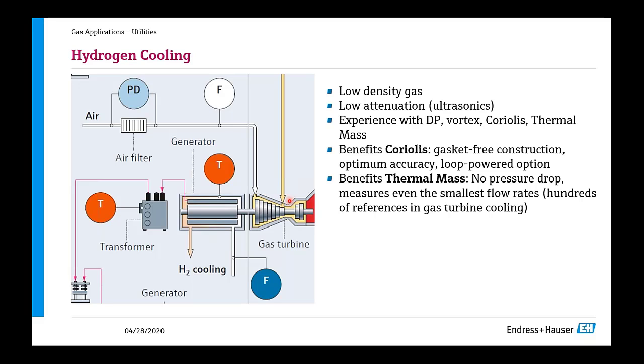We as Endress+Hauser have a lot of experience in this application using DP, vortex, Coriolis and thermal mass. I do like the Coriolis in this application because of its gasket-free construction and its optimum accuracy, and you find a loop-powered option as well. The thermal mass is, however, used quite a bit. We've got hundreds of references in the US especially. Here you have no pressure drop. It measures even the smallest flow rates, with hundreds of references in gas turbine cooling, with GE.